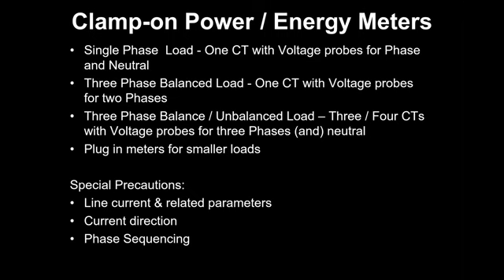For that, there is a simplified meter which will have one CT, because we are assuming that all three phases' load is the same. What we do is measure the current of only one CT, one cable, and measure the voltage for two phases. Now those two phases, depending on the meter, can be different phases. Like if you're measuring the power consumption in R phase, then the voltage could be connected to Y and B, or there are some meters which will say R and Y. So you go as per the manufacturer's directive and connect the voltage probe. Based on the assumption that all three phases have the same load, it will give you the data. It will give voltage, current, power factor, harmonics, everything.